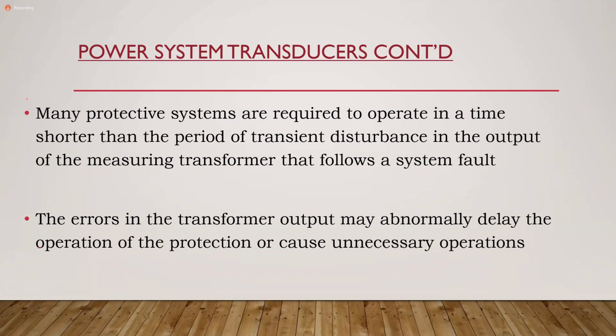Okay. Yes. What measures the current on the system would really be your relay. So your CT is just producing the scaled replica, or your VT producing the scaled replica. In terms of measuring, which is where now we're going to process. Because remember, we spoke about detection. Yes, sir. So detection is really a CT. So it's detecting and providing scaled replica. The relay now receives that and makes decisions based on what has been received. Okay, sir, understood. Good.